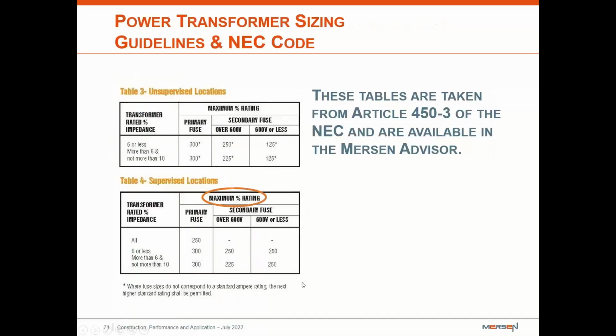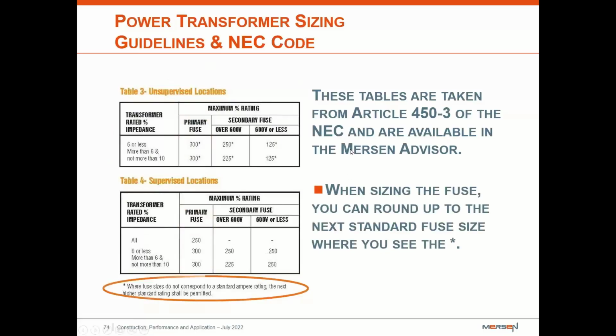So getting into the actual guides for these, these are the tables taken from 450.3 of the NEC, and these are also available in the Mersen Advisor. So you can see that it's specified as far as the primary fuses. For primary fuses up to 300%, the secondary fuses up to 250. If it's over 600 volts, for under 600 volts will be 125, and these are for unsupervised locations. For table 4, which is your supervised, for all fuses it's going to be 250 or 300%, if it's going to be 6% impedance or less, and then in the secondary for over 600 volts will be 250. And also for 600 volts or less. And where the fuses do not correspond with the standard size, so if you get a weird number, it is okay to go up to the next highest standard.